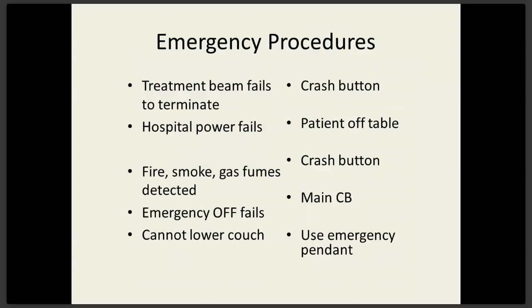So what to do if certain things go wrong in the room? If a treatment beam fails to terminate, there are crash buttons everywhere. They're on the console, they're in the room, they're on the couch. If hospital power fails, you've got to get the patient off the couch. You need to know how to use emergency pendants. Fire, smoke, gas: again, crash button, main circuit breakers. The main circuit breakers are always located near the console area, very, very handy nearby. When in doubt, crash the machine. Ask questions later.